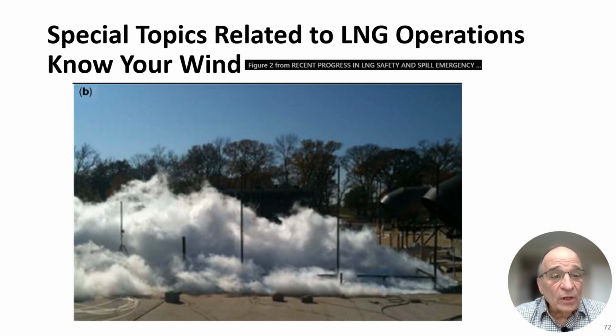This picture clearly shows why you should know your wind. In the event you have a spill, would you want to be on the right side of the spill or on the left side of the spill? Your muster point should be on the right side of the spill, not the left. Also, this shows that LNG vapors coming off of an LNG pool hug the ground. They do not rise. There are many people who think, well, natural gas is lighter than air, so the gas coming off of an LNG pool, the boil off, will vaporize and rise. But they won't, because they're so cold that they are heavier than air. LNG boil off becomes buoyant at about minus 150 degrees Fahrenheit. The vapor coming off of a pool of LNG is approximately minus 260 degrees Fahrenheit, which is denser than air at that temperature.